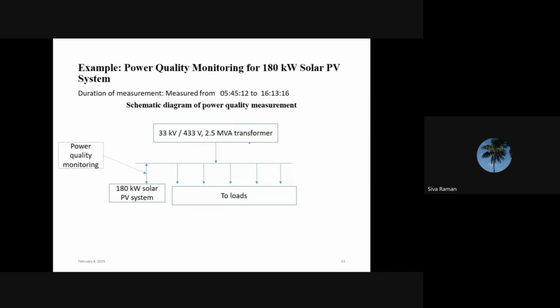So it is a typical block diagram. In this example, we have performed the power quality monitoring for a 180 kilowatt solar PV inverter. It has a distribution transformer like this, connected to the 33 kV high voltage side. It has 433 volts on the low voltage side.